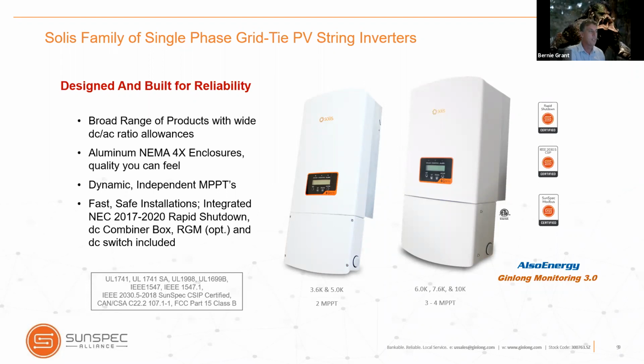What's interesting about our company versus other companies is our maximum power point trackers are fully 100% independent. So that gives you a little bit of flexibility in design. You don't have to worry about whether or not you have 9 or 10 panels on every string. You can have 2 of the strings on this big unit have 10 panels, and one string have 4 or 5 panels. It still operates very efficiently, and it's designed to help with complicated roof systems where you may have different portions of your array facing different directions.